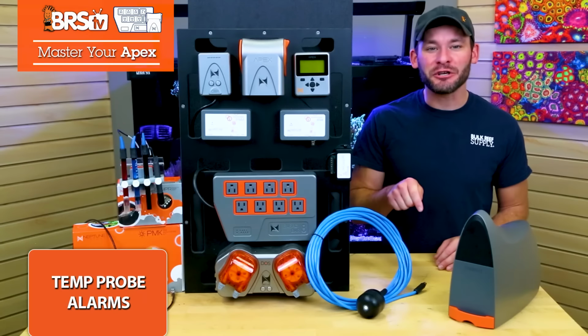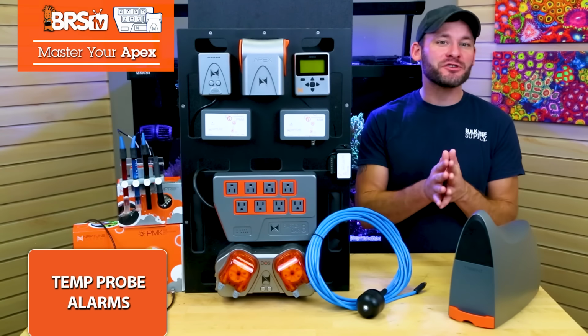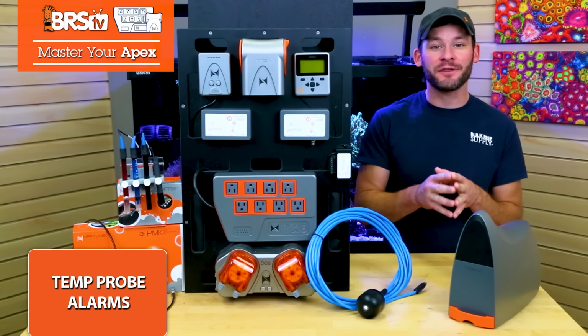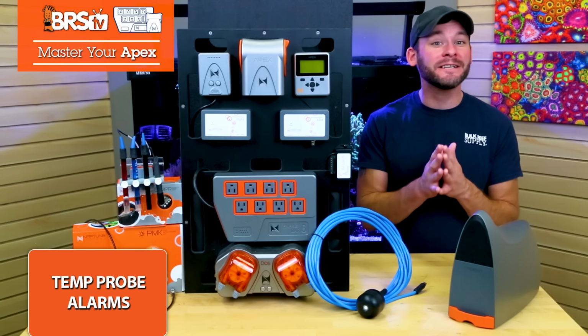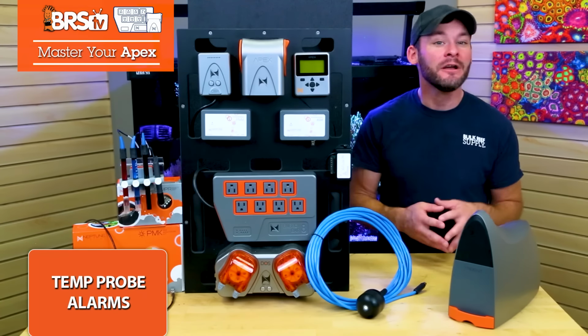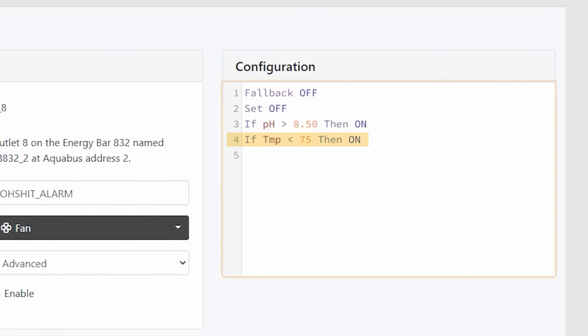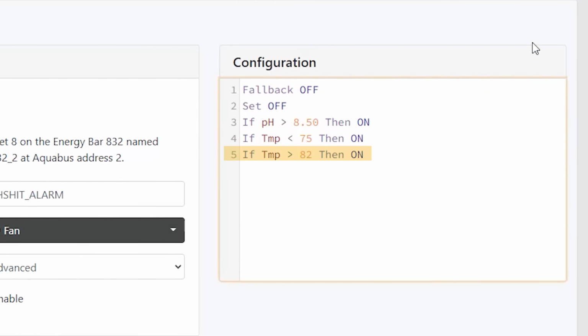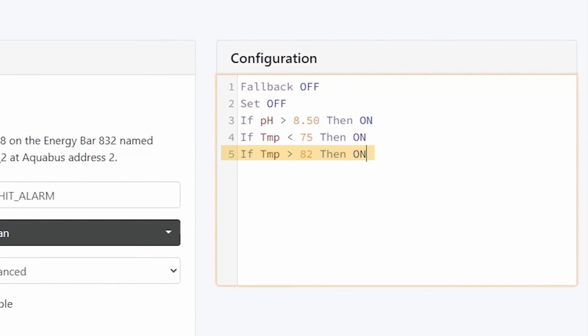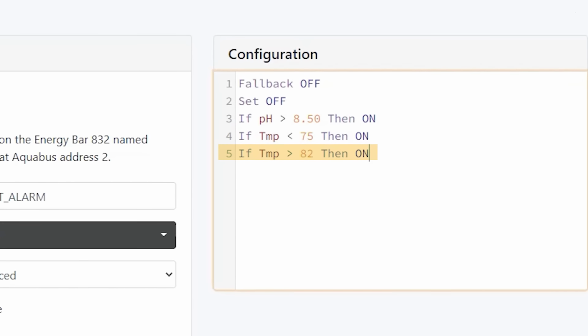Since that temperature alert is so mission critical, I'm also going to add this one into the outlet for the loud horn, radio, or audible warning device that we set up earlier by clicking on that outlet's gear icon and adding 2 new lines that say, if temp less than 75, then on, and if temp greater than 82, then on, so no matter what we're doing when these things go wrong, there's no chance that we miss it.